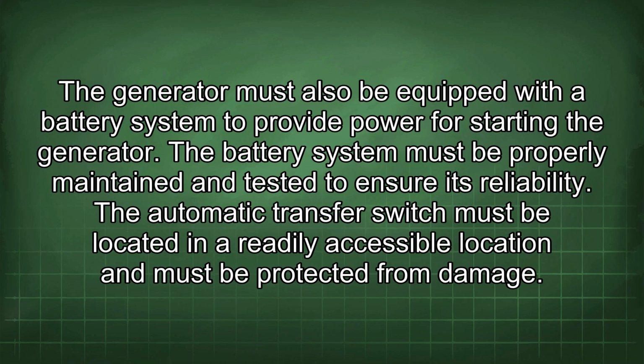The generator must also be equipped with a battery system to provide power for starting the generator. The battery system must be properly maintained and tested to ensure its reliability. The automatic transfer switch must be located in a readily accessible location and must be protected from damage.